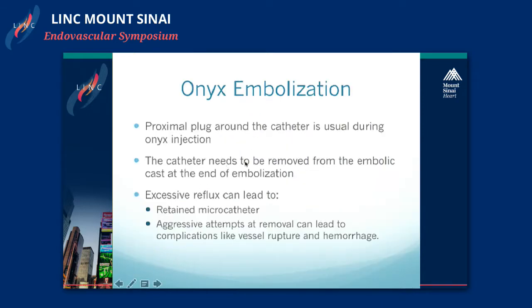A proximal plug is used and the catheter needs to be removed from the embolic at the end of the embolization. Even though Onyx is not adhesive, if you reflux too much along the catheter, this can lead to a retained microcatheter because of friction when trying to remove it. And if you then pull too hard, this can lead to rupture and hemorrhage.